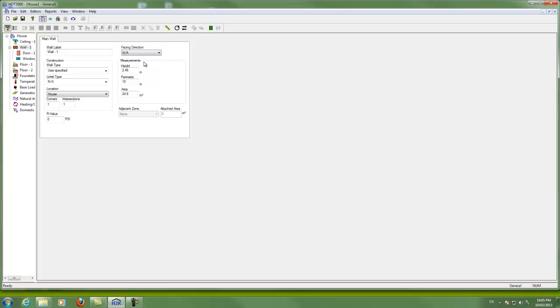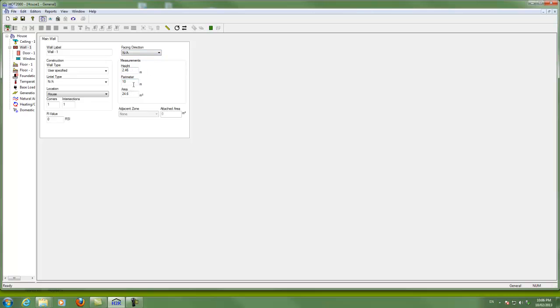And you can enter your entire wall that has that same construction using the height and the perimeter. So if I had, for instance, the first story of a house was a 2x4 R12 insulated wall with some sheathing and drywall and such, I could put not applicable for direction, put the height of that wall and the perimeter. Height times perimeter will give us the area of the wall. And that's the area that Hot 2000 is going to use for heat loss.